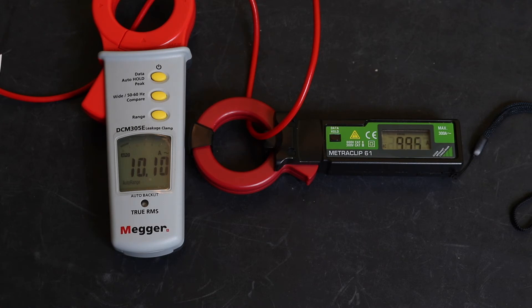Let's go down to 5 amps, 2.5 amps. 2.45 on the Metrawatt and 2.529 on Megger. We're going to go down to 1 amp. 1.018 on Megger. And 0.96. Again a little bit less stable on the Metrawatt whereas the Megger is pretty much there solid.